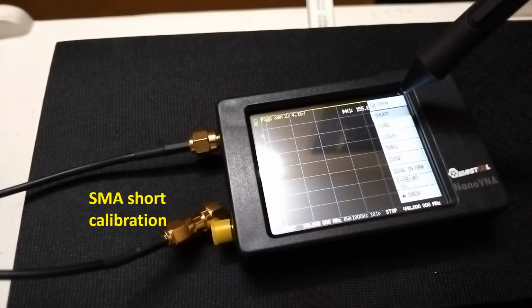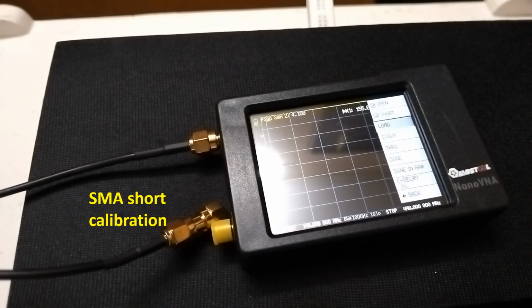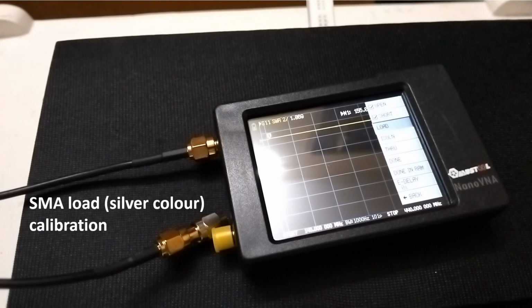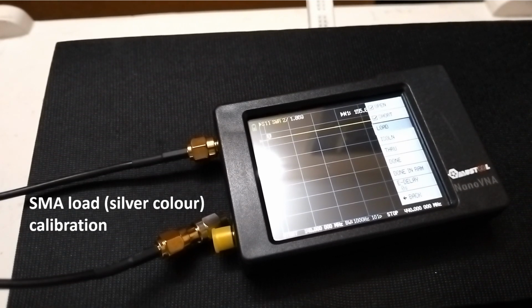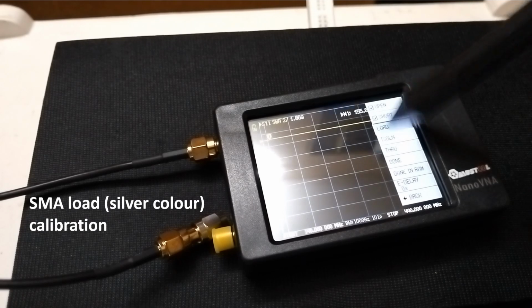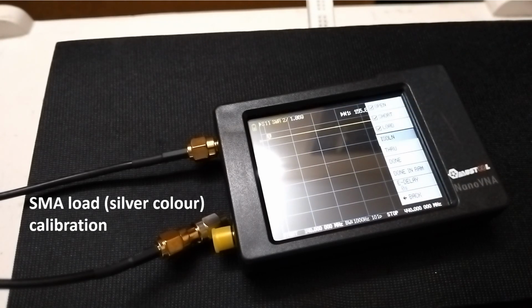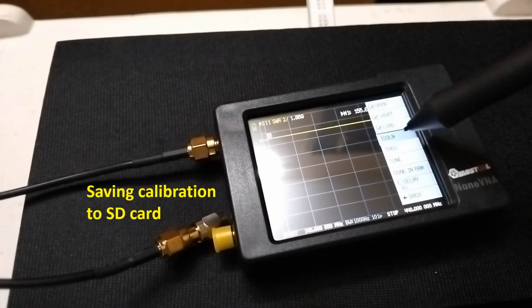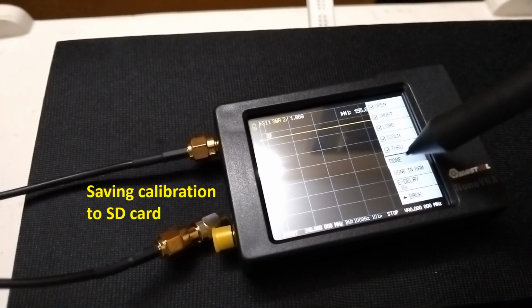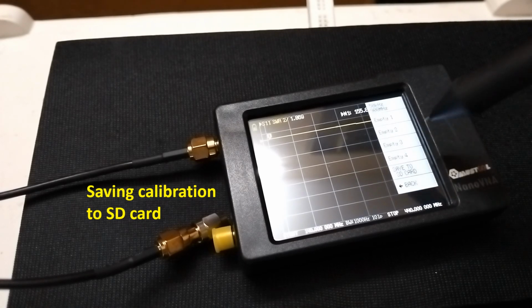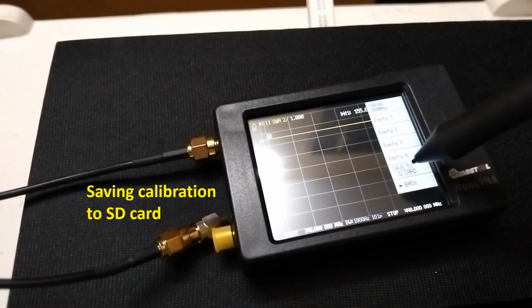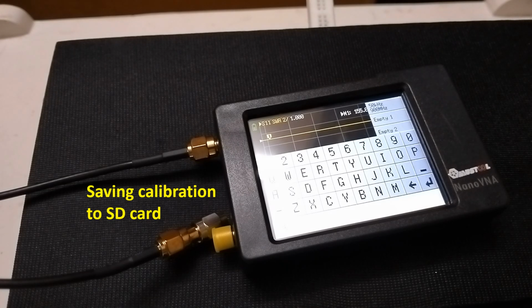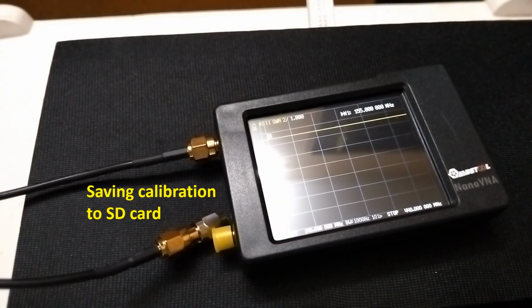The SMA short has been connected. Now I'll press short. So that has also been calibrated. Tick mark has appeared. The SMA load has been connected. It has a silvery color. Now the load has also been calibrated. Now I am going to save it to SD card. I will save it in channel 2. So the calibration has been saved.